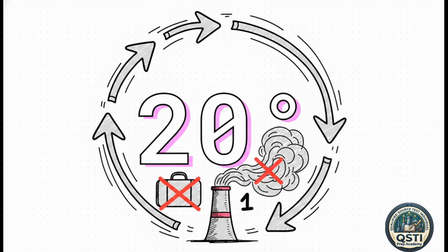And that brings us to the magic number for cyclonic flow, 20 degrees. Once you've got the rotation angle for every point in the stack, you calculate the overall average of the absolute values. If that average is greater than 20 degrees, no way. The flow condition is totally unacceptable. You literally pack up your bags because you cannot use standard Method 1 there.